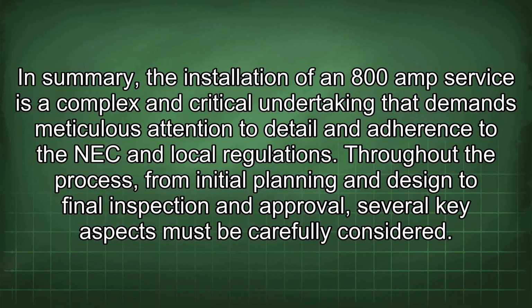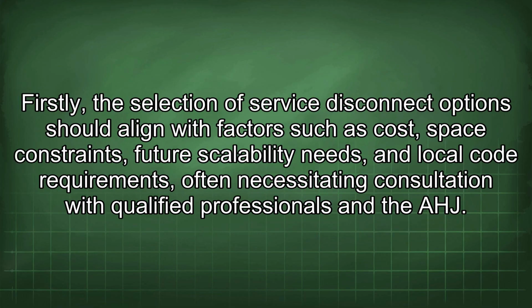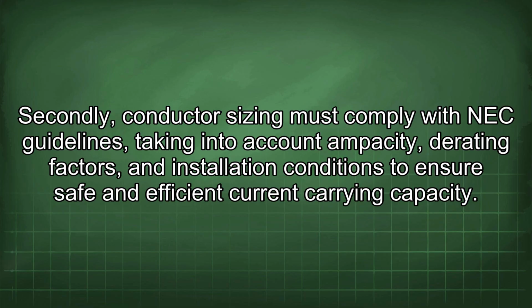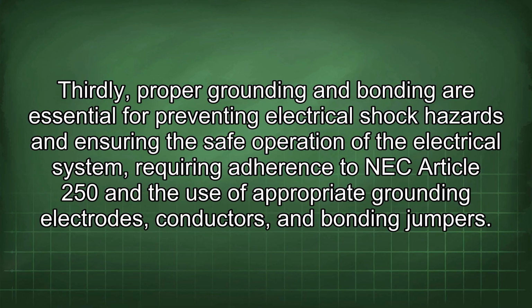Throughout the process, from initial planning and design to final inspection and approval, several key aspects must be carefully considered. Firstly, the selection of service disconnect options should align with factors such as cost, space constraints, future scalability needs, and local code requirements, often necessitating consultation with qualified professionals and the AHJ. Secondly, conductor sizing must comply with NEC guidelines, taking into account ampacity, derating factors, and installation conditions to ensure safe and efficient current carrying capacity. Thirdly, proper grounding and bonding are essential for preventing electrical shock hazards and ensuring the safe operation of the electrical system, requiring adherence to NEC Article 250 and the use of appropriate grounding electrodes, conductors, and bonding jumpers.